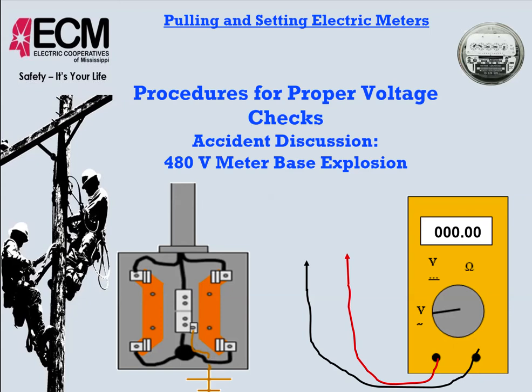So he went in and took the inside breaker box out, and to get it to go back through that knockout, that hole that they're fed through coming from the meter base, he had to take all the hots and the neutrals and twist them together. So had he tested for that, even though the meter had been taken off and he was putting it back on in a short amount of time, had he done his proper checks each and every time before he set a meter, this would not have happened.